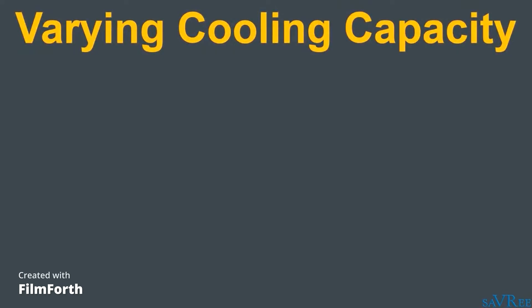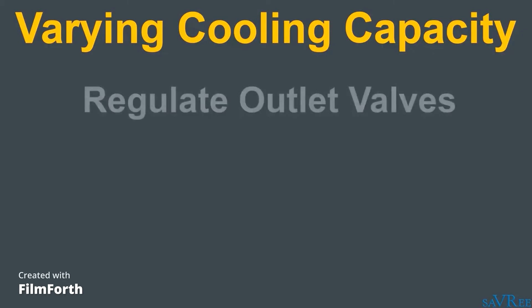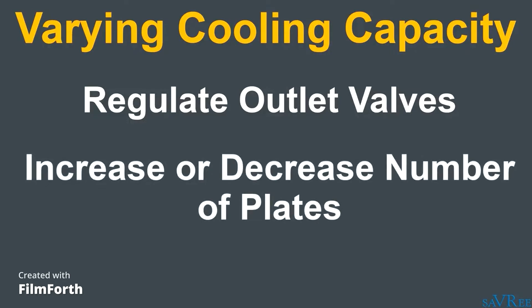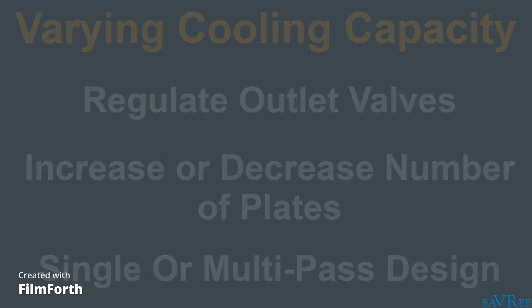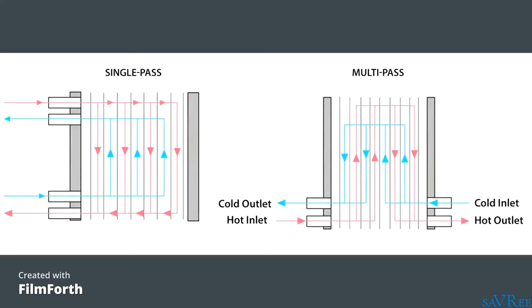There are several ways to vary the cooling capacity of a heat exchanger. One way is to regulate the outlet valves to increase or decrease flow — useful because no dismantling is required. Another way is to increase or decrease the number of plates in the plate stack; more plates equals more cooling, and less plates equals less cooling. The final method is to use a single-pass or multi-pass design. Single-pass heat exchangers allow the two flowing mediums to flow past each other only once, while multi-pass heat exchangers allow them to flow past each other several times. Most plate heat exchangers use the single-pass design.